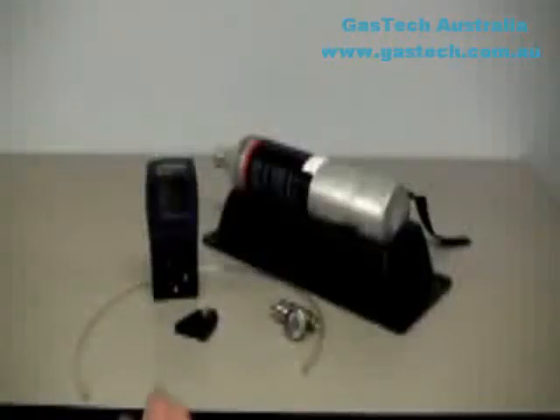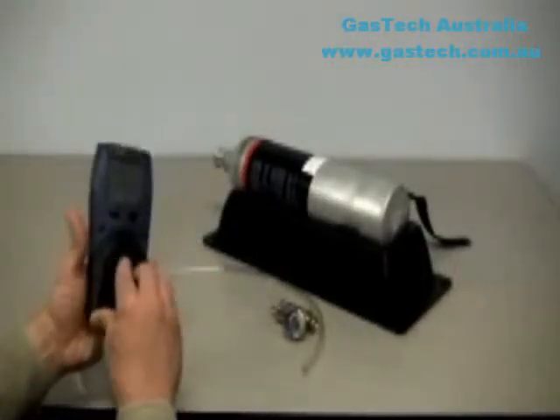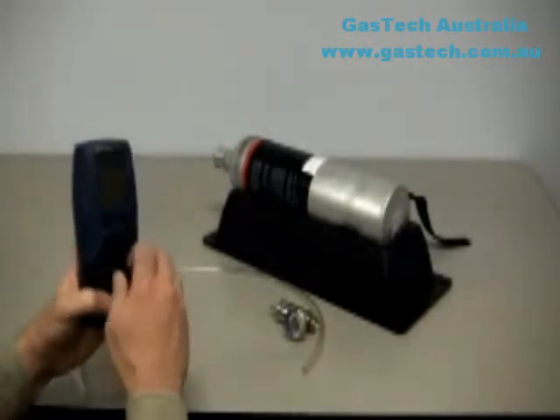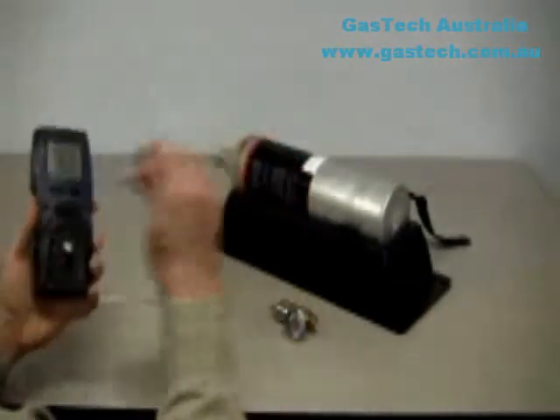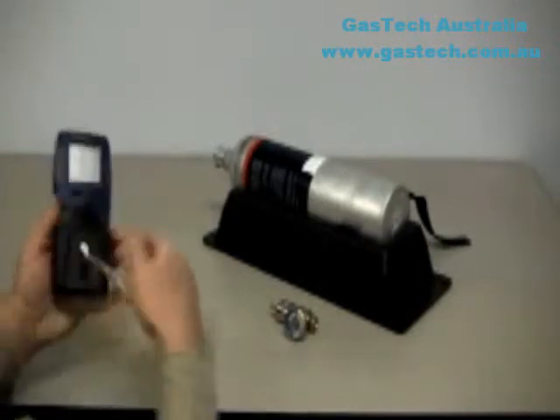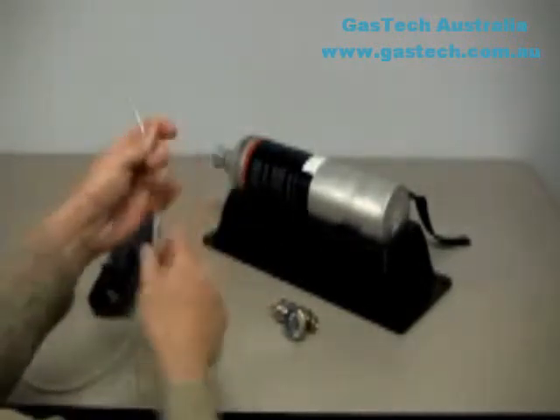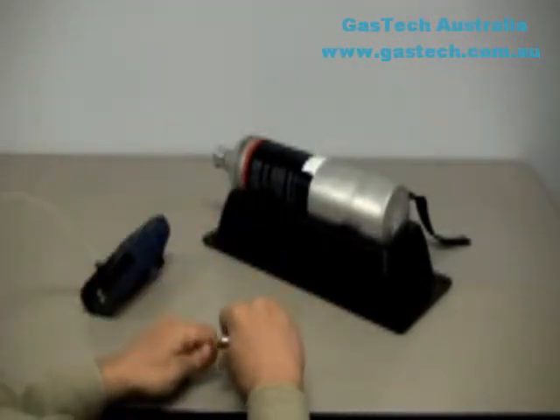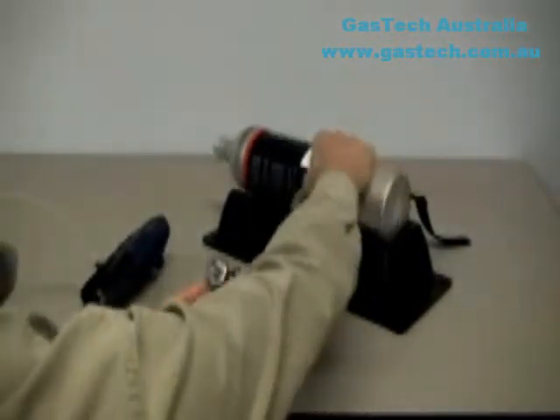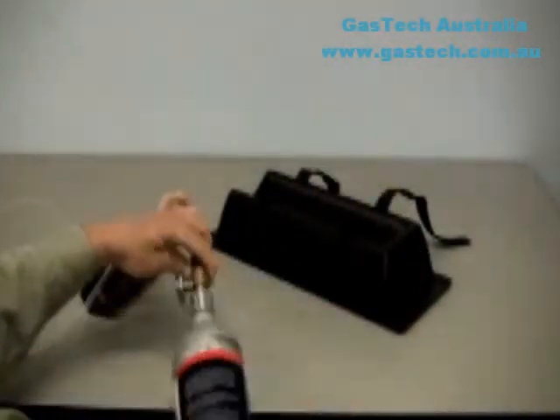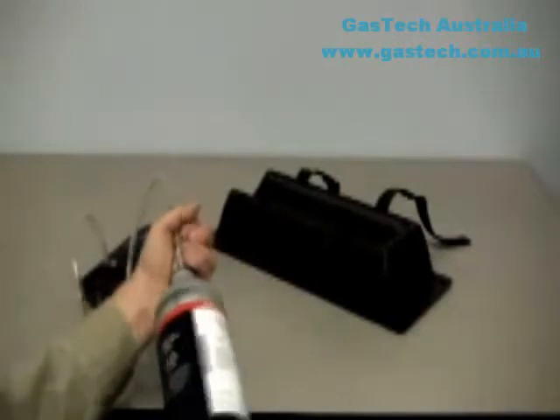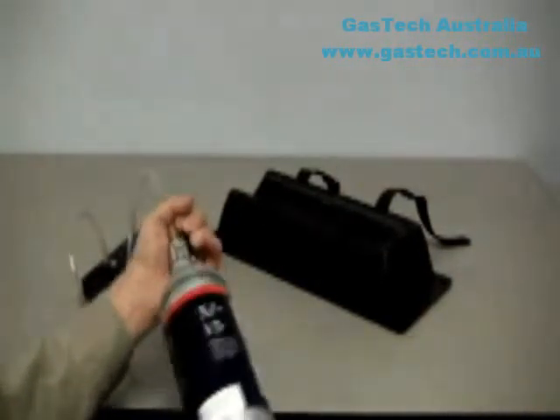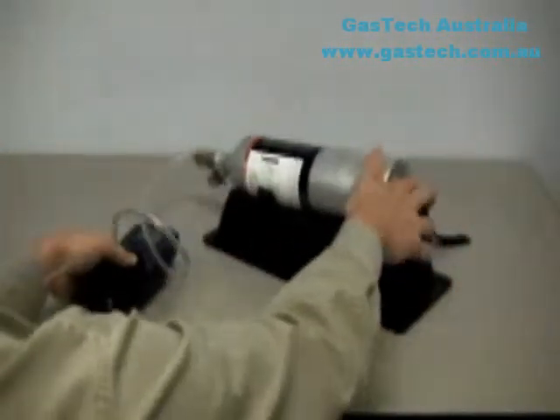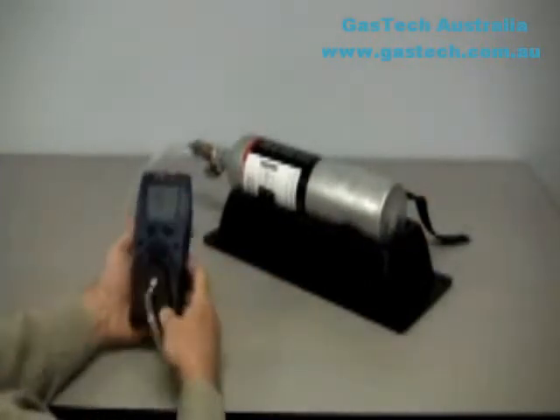To perform a bump test, attach the calibration gas cylinder, regulator, and calibration adapter with a short section of tubing to the PHD6. Make sure that the cylinder threads and seating surfaces are clean and dry when attaching the regulator to the gas cylinder. All-in-one calibration mixtures are especially convenient when doing a bump test. Flow gas to the sensors and allow the readings to stabilize. 45 seconds to 1 minute is usually sufficient.